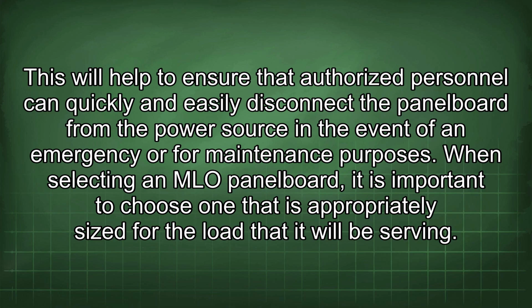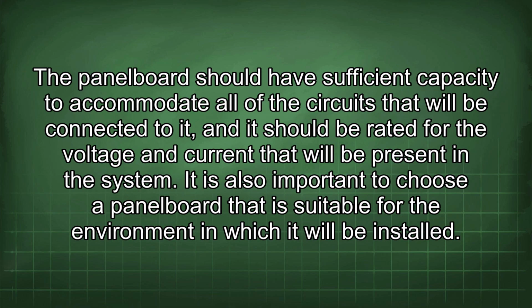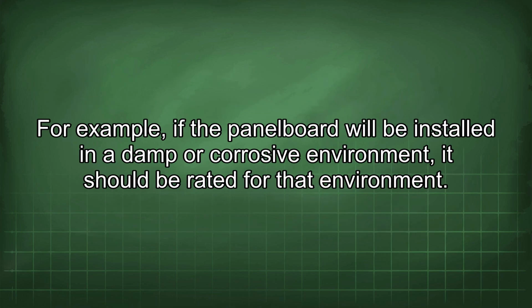When selecting an MLO panel board, it is important to choose one that is appropriately sized for the load that it will be serving. The panel board should have sufficient capacity to accommodate all of the circuits that will be connected to it, and it should be rated for the voltage and current that will be present in the system. It is also important to choose a panel board that is suitable for the environment in which it will be installed. For example, if the panel board will be installed in a damp or corrosive environment, it should be rated for that environment.